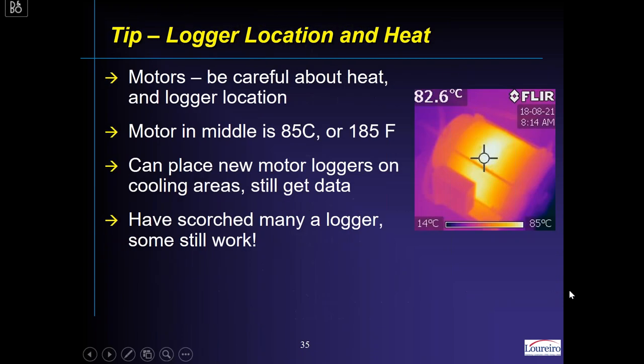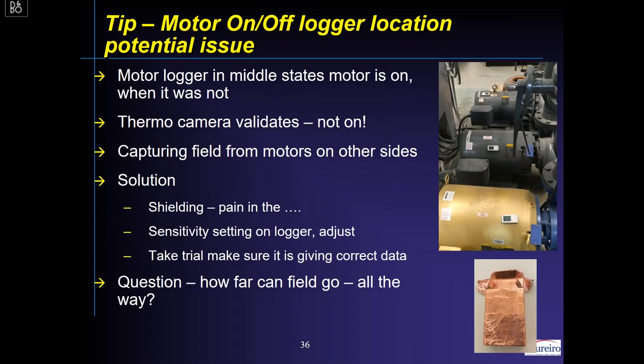Be careful about heat when placing motor loggers — this comes from experience having scorched some loggers that no longer work. Motors can get hot. We almost always use a thermal camera or infrared thermometer first. This particular motor is 85°C or 185°F in the middle — you can put a motor on/off logger on it, but I would not put it over the 185°F hot area. Place it towards the two sides of the motor which may be under 100°F. That difference can matter a lot, and you may not have a logger left when you return.